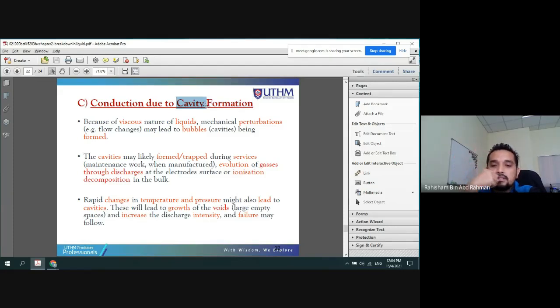Cavity means a void within the material. Once we have a void, the dielectric strength will be different, as well as permittivity and conductivity, and hence that will trigger localized discharge within the void. Once we have localized discharge, this can grow bigger. That is more critical if the void is near the high voltage terminal, because there we have a high electric field, and with the current, that could trigger a more intense discharge activity within the gas in the void. That is due to cavity.